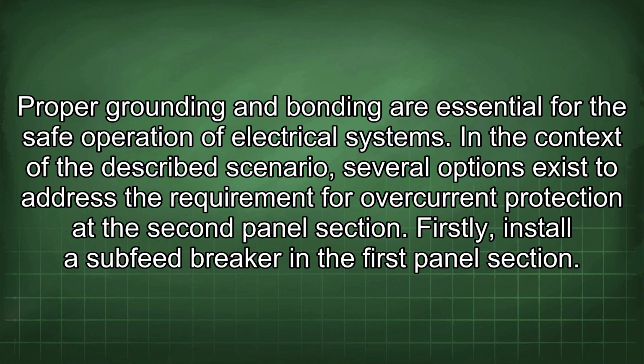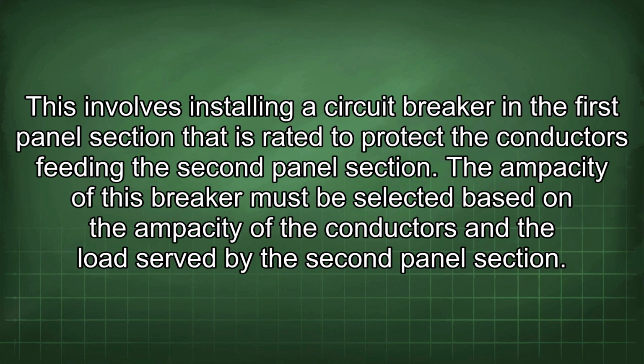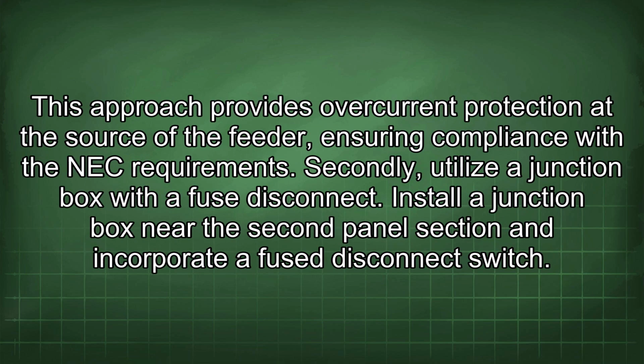In the context of the described scenario, several options exist to address the requirement for overcurrent protection at the second panel section. Firstly, install a sub-feed breaker in the first panel section. This involves installing a circuit breaker in the first panel section that is rated to protect the conductors feeding the second panel section. The ampacity of this breaker must be selected based on the ampacity of the conductors and the load served by the second panel section. This approach provides overcurrent protection at the source of the feeder, ensuring compliance with the NEC requirements.